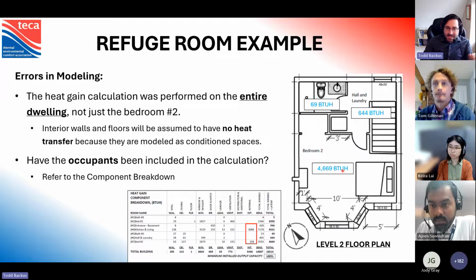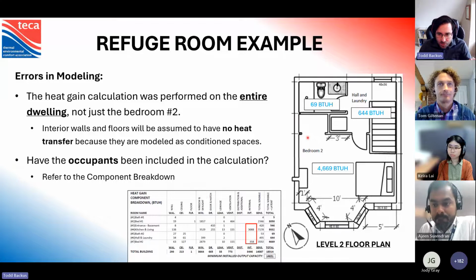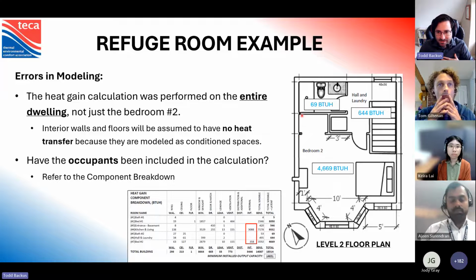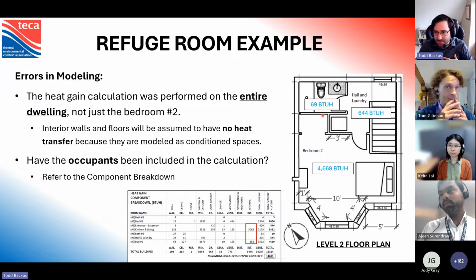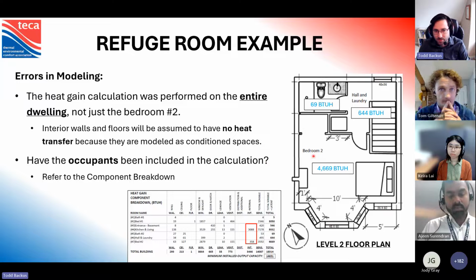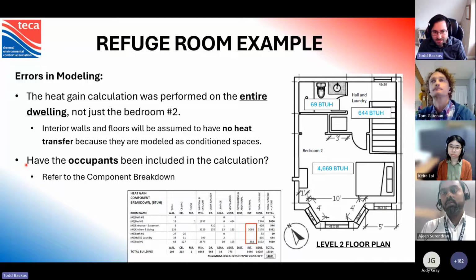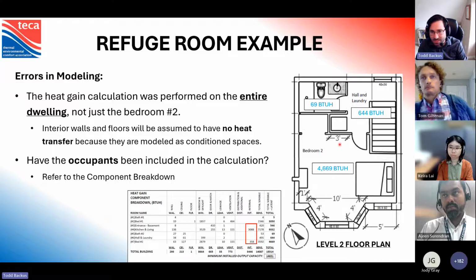Now, this gets a little bit confusing and difficult to deal with, because there is no clear standard for how you are specifically supposed to model this. All the code says is that you have to maintain 26 degrees C in one space. So be aware, this is my approach to meeting this requirement, but it is absolutely justified to say that modeling the whole house and then cherry picking one room is not a reasonable approach. So you've got to look at things like, have the occupants been included in here? Have the electrical considerations been taken into account?